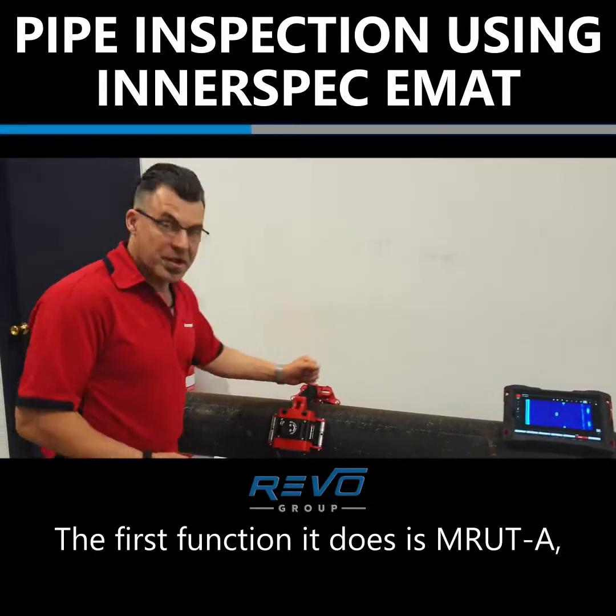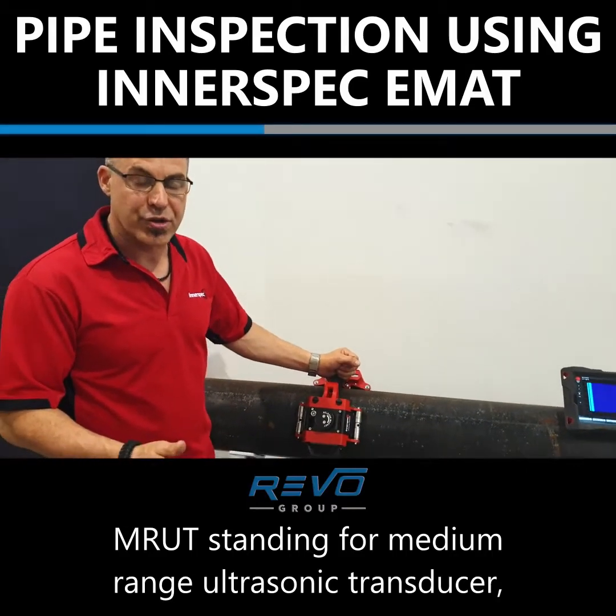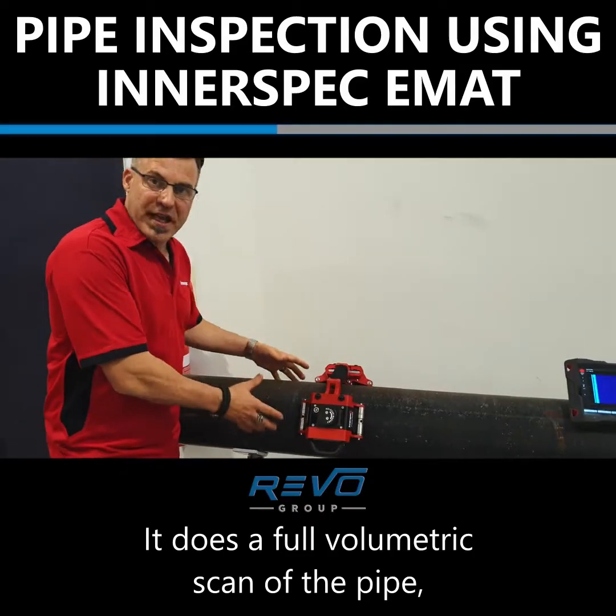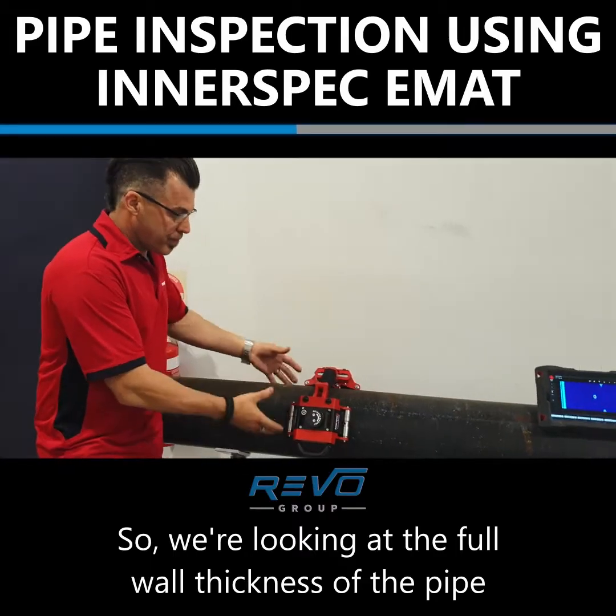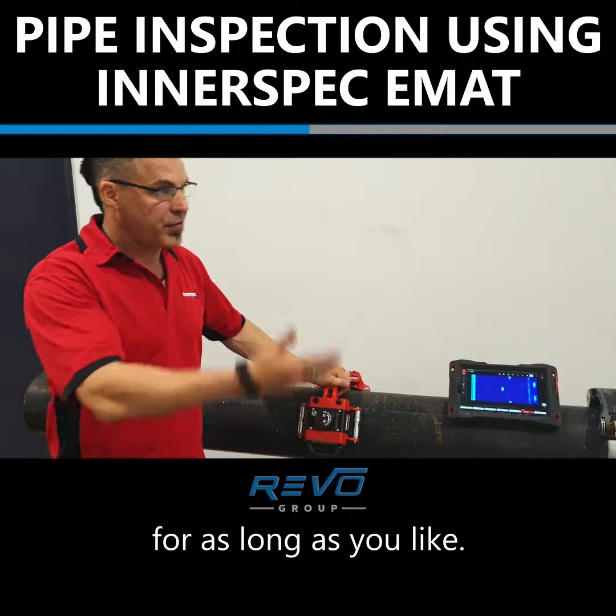The first function it does is MRUT A — MRUT standing for medium range ultrasonic transducer, A for axial. It does a full volumetric scan of the pipe and moves axially. So we're looking at the full wall thickness of the pipe right the way around and we can scan at walking speed for as long as you like.